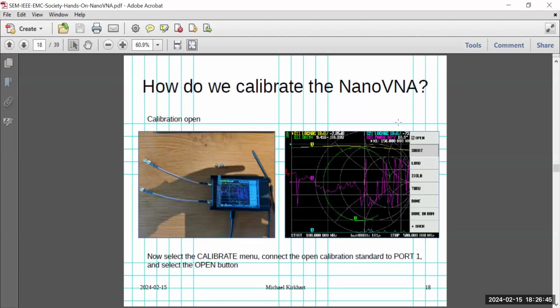And then the next thing is the calibration open. With the through adapter on there, go ahead and take the open standard. You're probably wondering which one is the open. If you pull these calibration standards out, that's the load. That's the short. So the open is the one that doesn't have a pin. Okay. Once you connect that up to port 1, not port 2, port 1, the next thing you'll do is hit the calibration menu. Let me go back up here one.